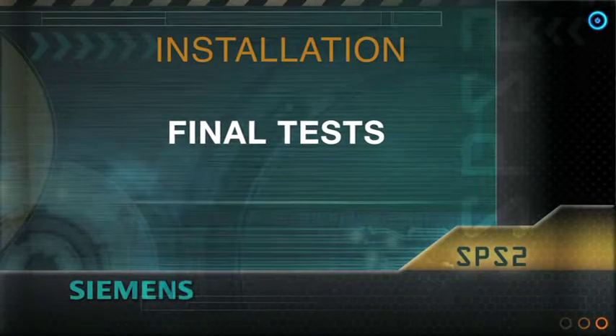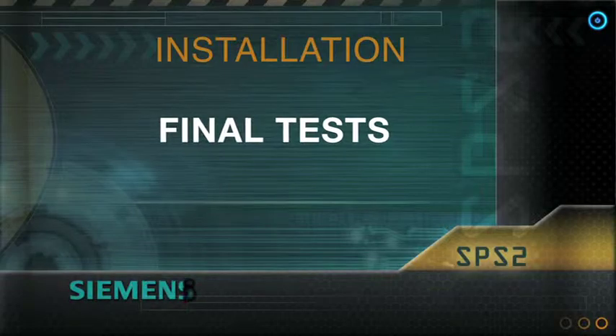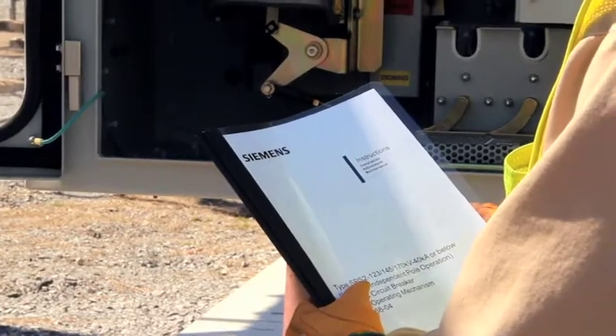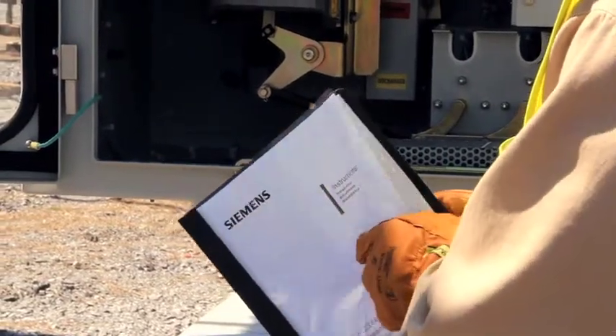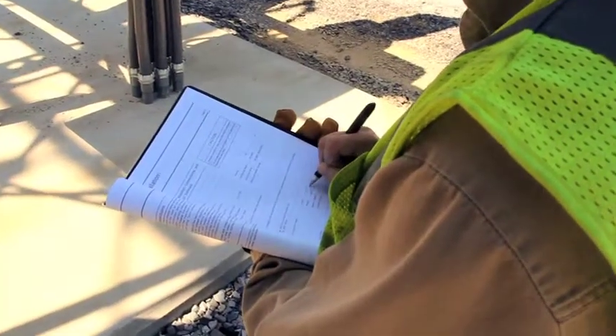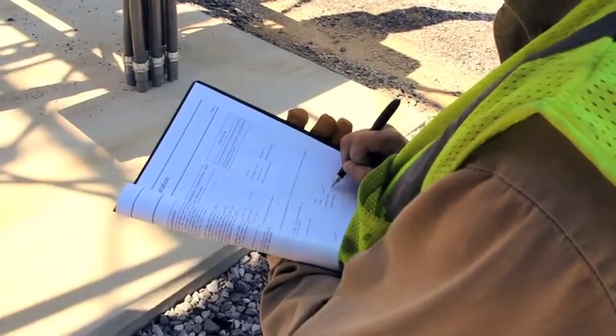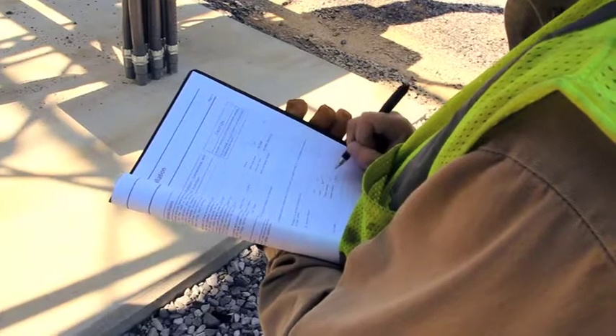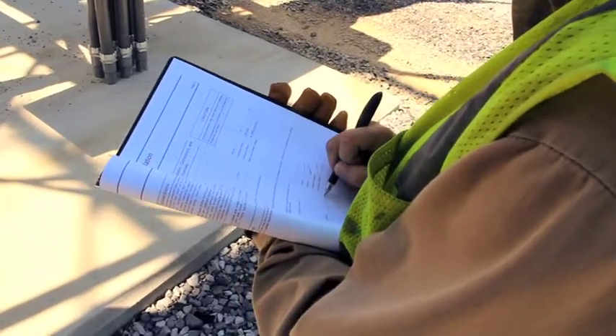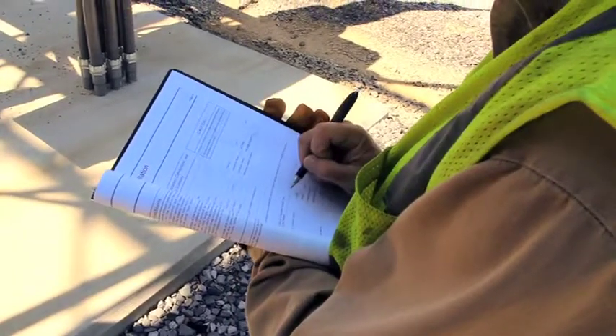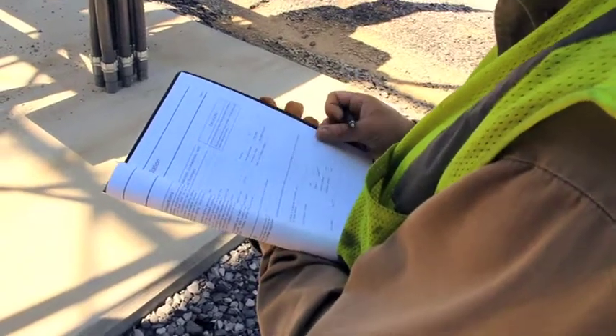Installation. Final tests. An effective maintenance program begins at the installation, for which a detailed checklist is inside the instruction manual. This information is then used as a baseline reference for future maintenance and should be a permanent record for each circuit breaker. This should be the complete records of installation, inspection, and maintenance work performed.